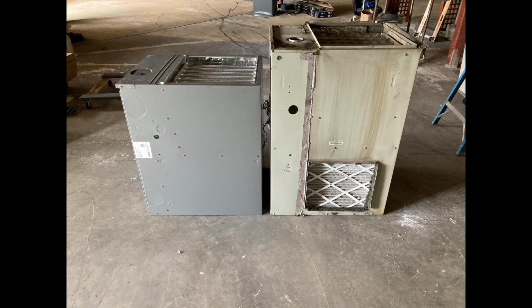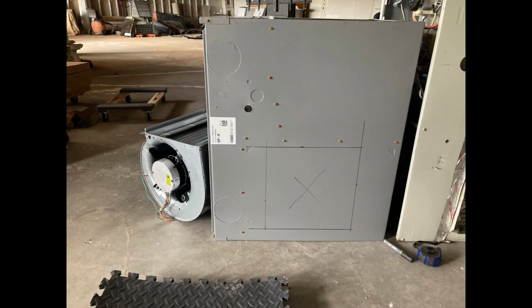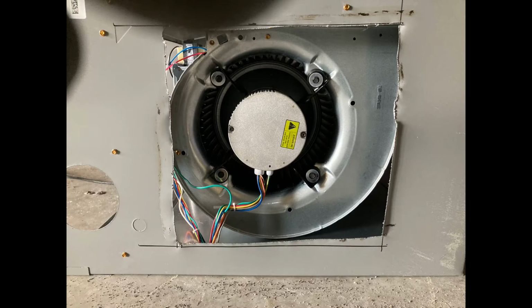Now I'm going to set the old air handler next to the new one, and I need to transfer some measurements for the air intake and cut the openings for the air intake on the side of the new air handler. First, I'll slide out the new blower motor assembly because I do not want to drill or cut into that while I'm cutting into the side of the air handler body. See everything marked? Everything's cut out. I'll clean up my cut. Slide the blower motor back in.